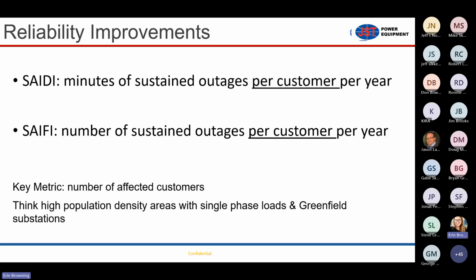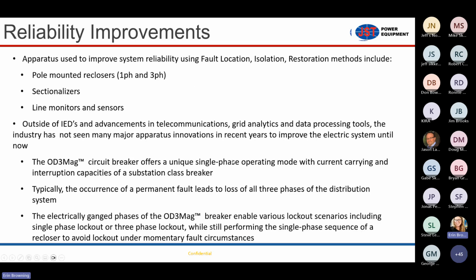So it's really going to be high population areas and new developments, and it could be pitched as an easy button for SAIDI and SAIFI improvements, because SAIDI and SAIFI are functions of number of customers. When you have a lot of customers packed into one small area, and you can do single phase trip, single phase close all the way back to the substation, you're going to have an immediate, significant impact on SAIDI and SAIFI. We've pitched this reliability improvement application since the beginning of our outdoor breaker, and I know a lot of you have come to us saying, look, it's not that easy. We recognize it. But there is still a case to be made when you're talking to customers about greenfield, new substations dedicated to serving new housing developments. We can talk more about this on the side if you have more questions.